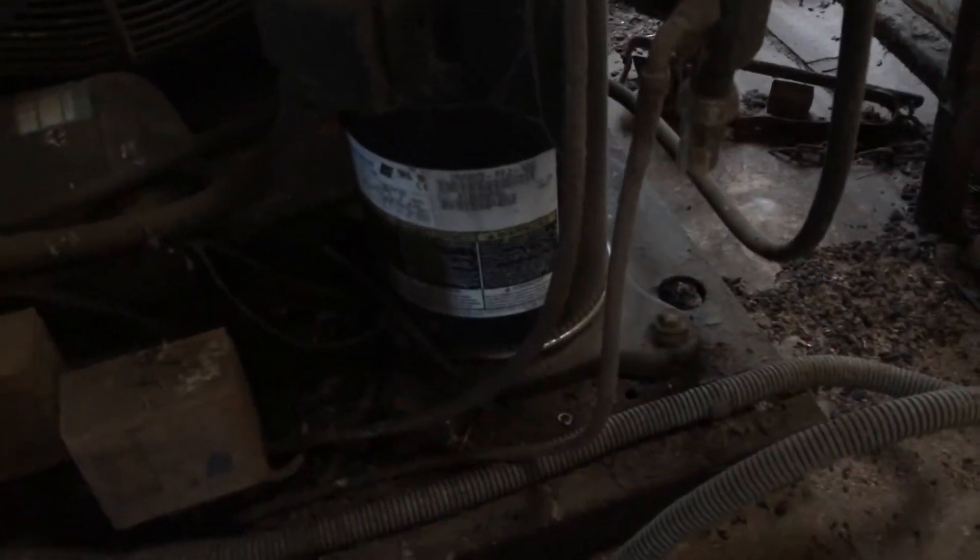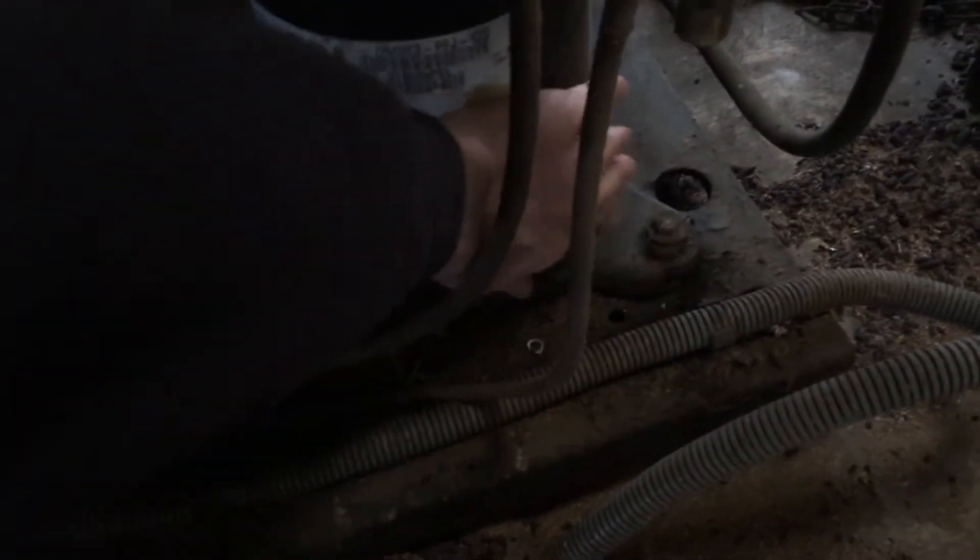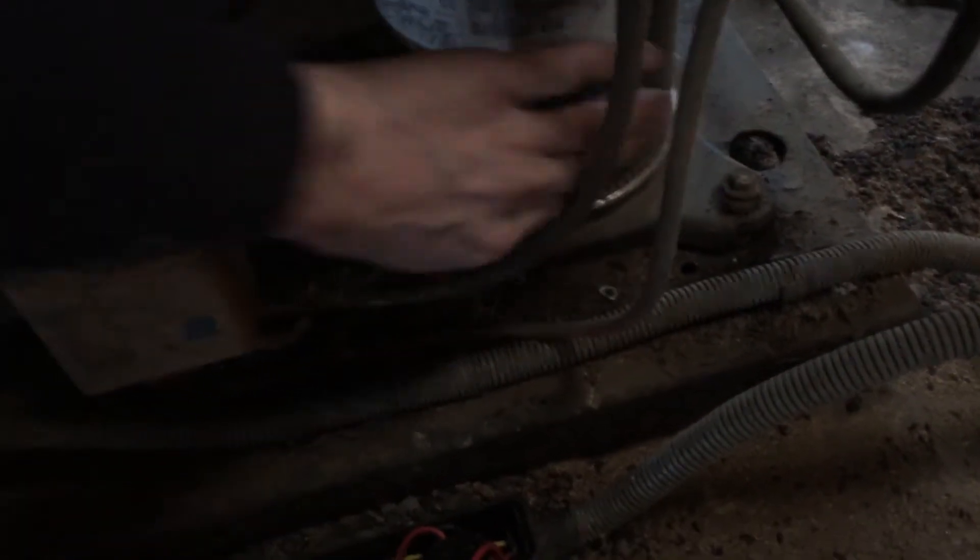Right, looking at this because the compressor's not running. First thing I've done is just touched the crankcase heater and that was cold, so it kind of points to there not being any power unless the heater is faulty.